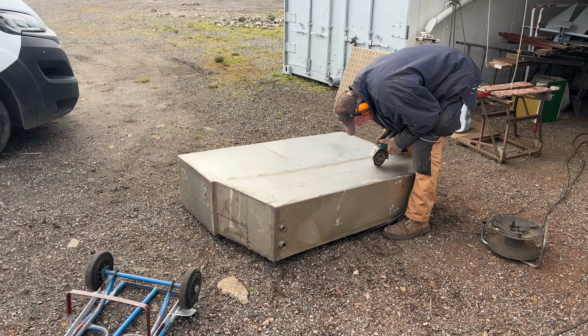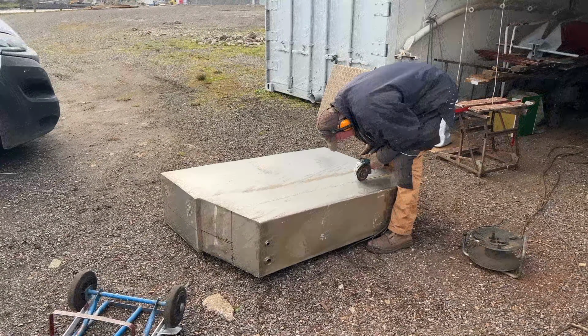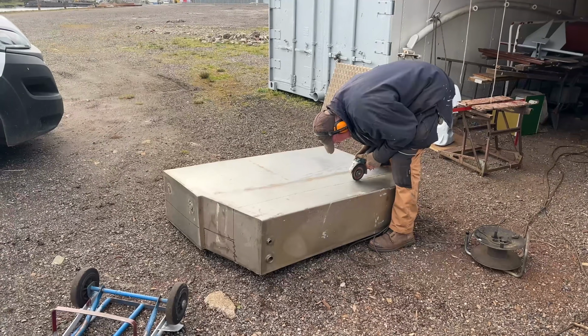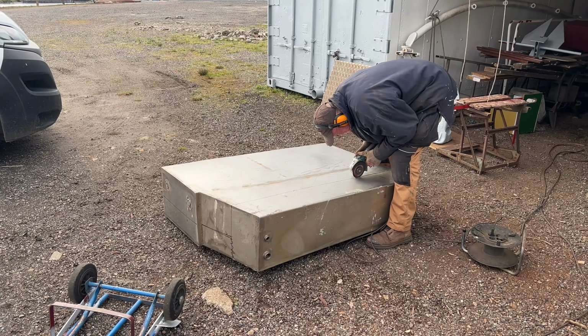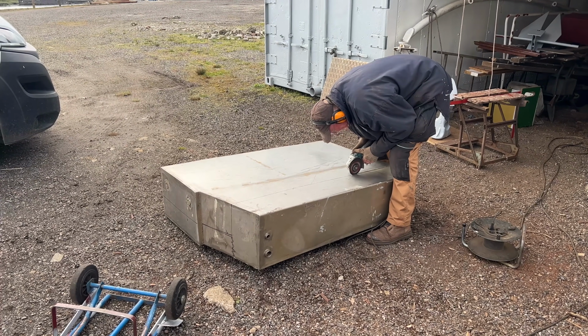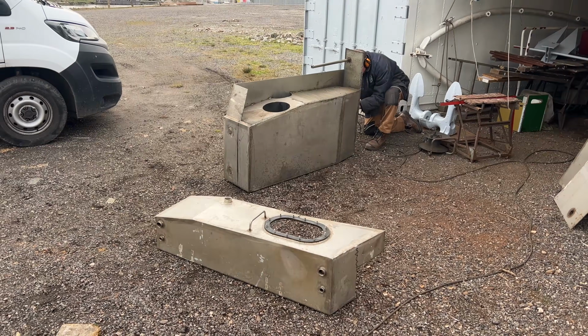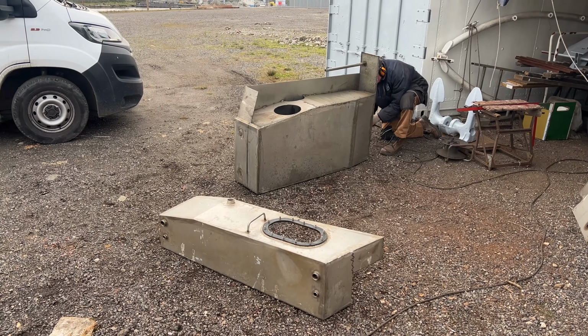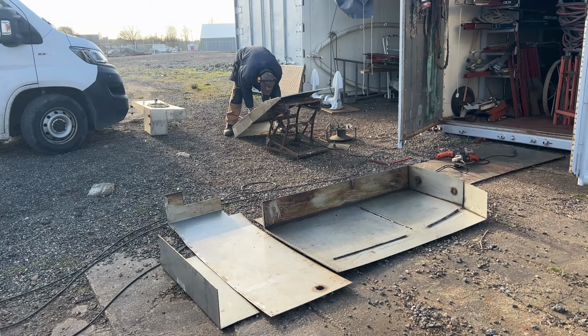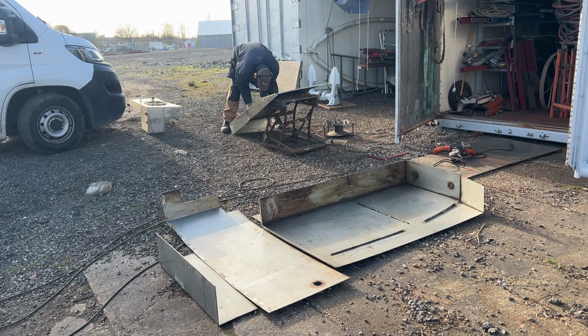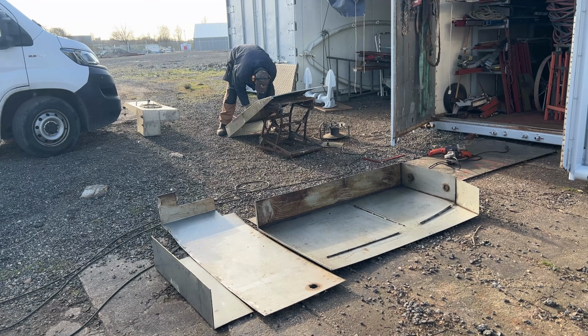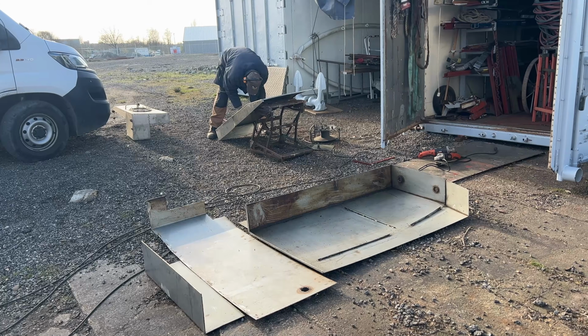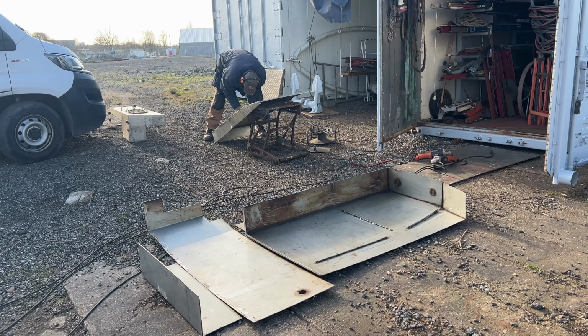But a proper high voltage and battery management system is only one part of minimizing the risk of thermal runaway. We also need an enclosure for the batteries. We have a used but still good stainless steel water tank laying around, and we can turn that into a battery box. That box can contain and help us fight any possible battery fire. The box has to be watertight to keep salt water out and fresh water in if we ever need to flood the battery pack to cool it down.